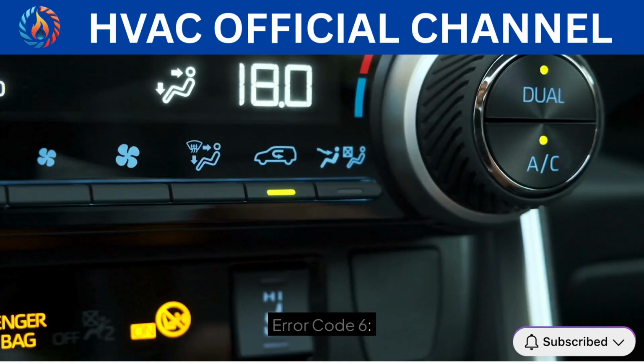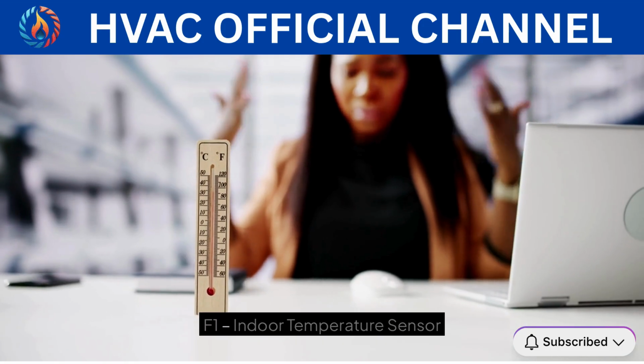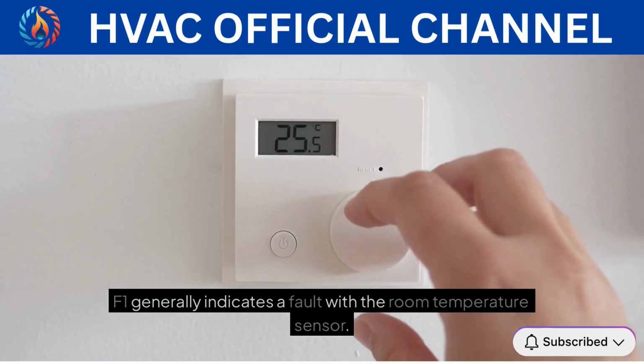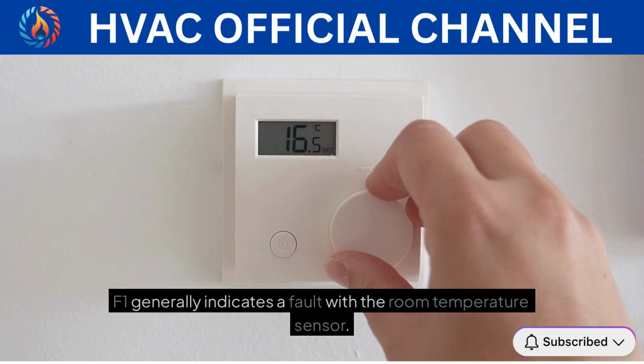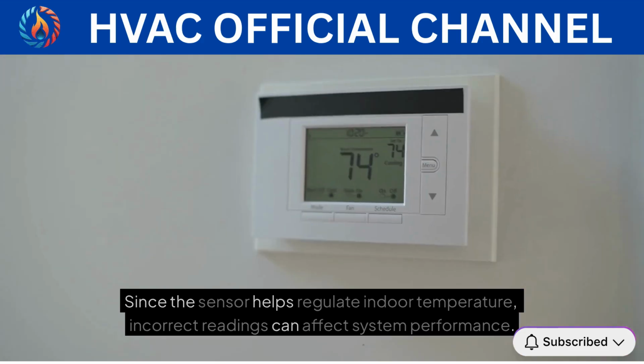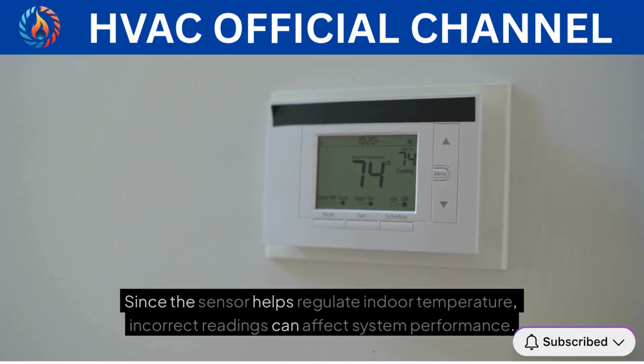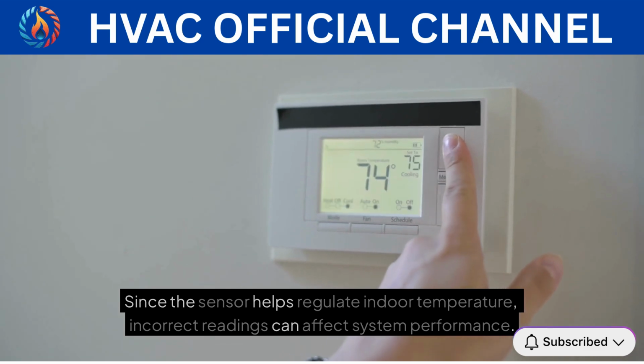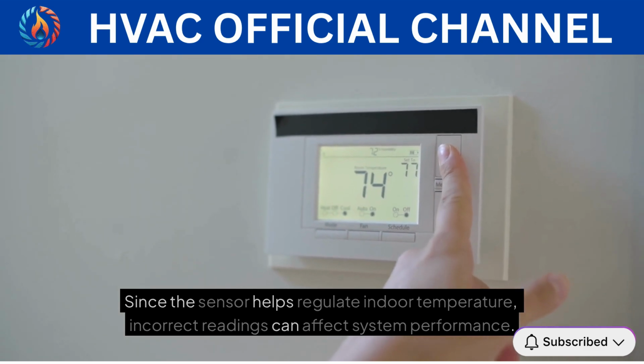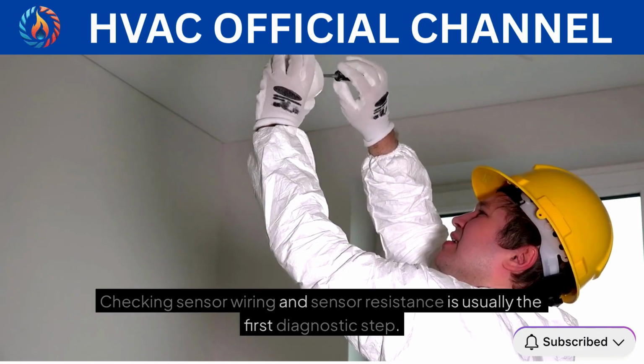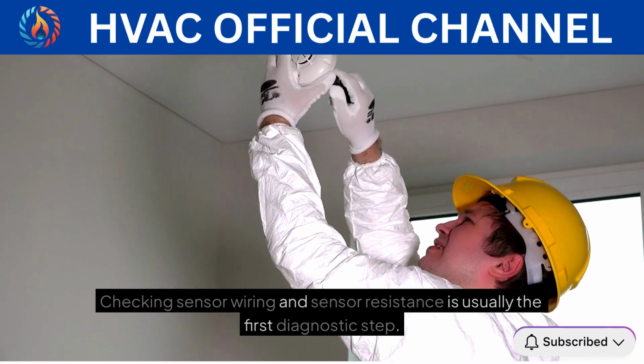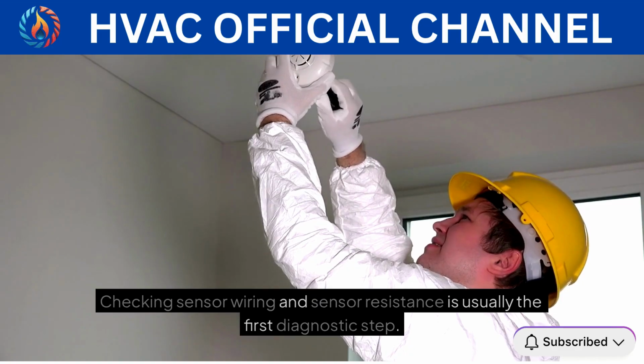Error code 6, F1, indoor temperature sensor error. F1 generally indicates a fault with the room temperature sensor. Since the sensor helps regulate indoor temperature, incorrect readings can affect system performance. Checking sensor wiring and sensor resistance is usually the first diagnostic step.